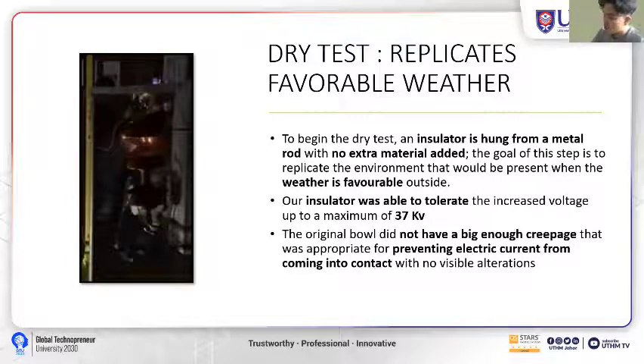The goal of the dry test is to replicate the environment that will be present when the weather is favorable to the insulator. And based on our insulator prototype, the insulator can withstand a maximum of 37 kilovolt. After the 37 kilovolt, a spark was produced, and the reasoning behind the spark is the original bowl doesn't have enough capability to prevent the electric current from coming into contact with the next disc.